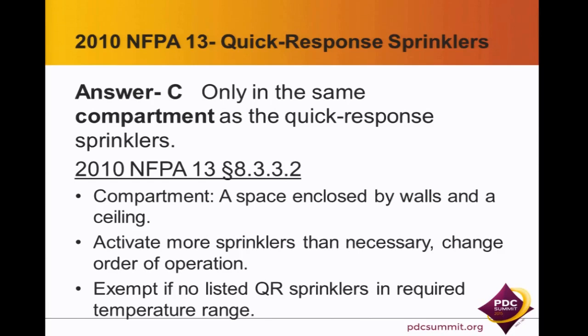Joint Commission's interpretation is the entire smoke compartment. So be mindful of that if you're doing a renovation project, that you will have to replace them throughout the entire smoke zone. Okay, George is back there shaking his head no, but I know that people have been told that. Yeah, it's this definition of compartment, and that's why we emphasize the word compartment, because it is the NFPA 13 compartment.